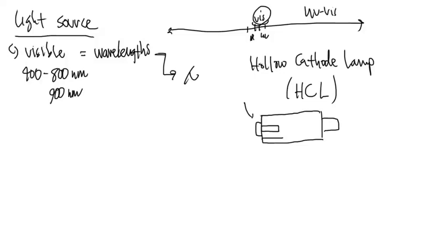On the lamp itself, there is a plug-in area. So this is where you would plug the lamp up into the machine. It typically has a couple of prongs that sit out here in the bottom. And then the light energy basically escapes through the front part of the lamp. And this is what goes and hits the atom of interest in the flame.